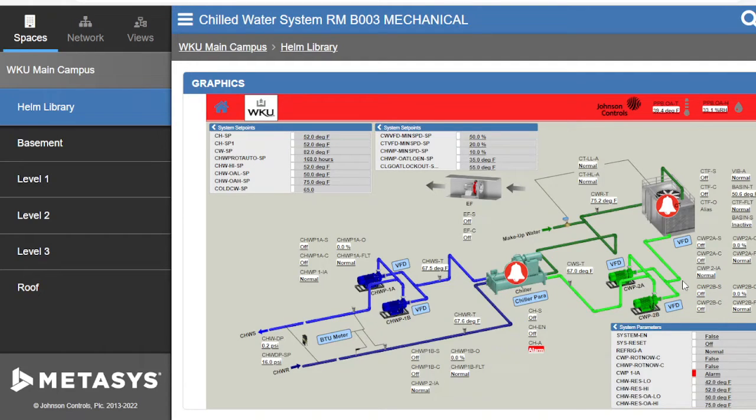And of course, many of you guys know, if you get into some of the CCT programming and things like that, CCT programs typically do not like overrides. The logic on a lot of the points, a lot of the logic blocks at that point will basically just shift to a hold state, and the logic will not always work properly. And so what we end up doing is creating a problem for ourselves.